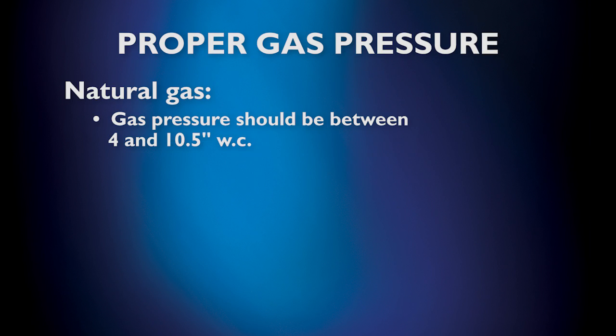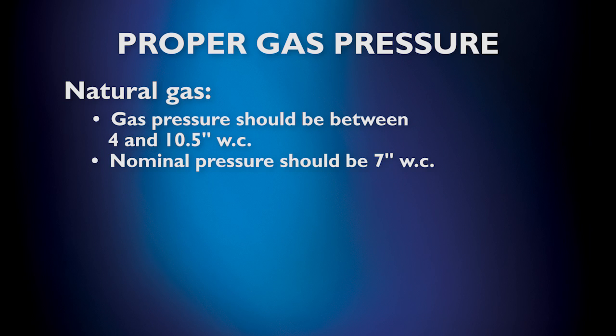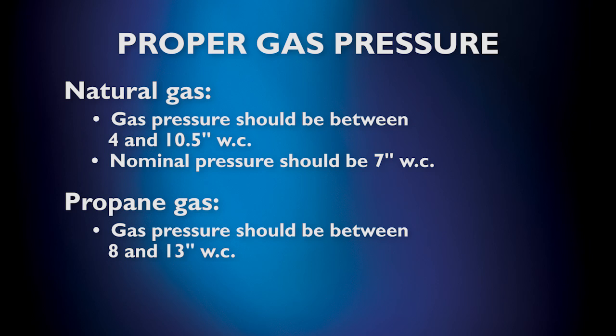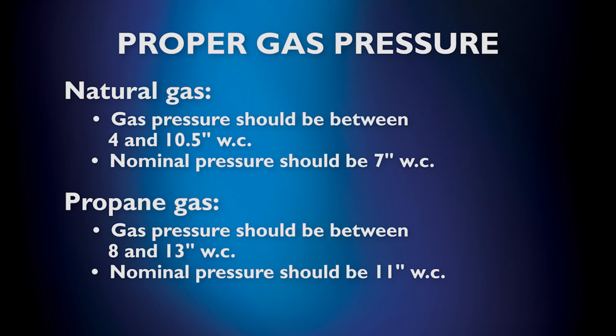For natural gas, the pressure should be between 4 and 10.5 inches water column. Nominal pressure should be 7 inches water column. For propane gas, the pressure should be between 8 and 13 inches water column. Nominal pressure should be 11 inches water column.